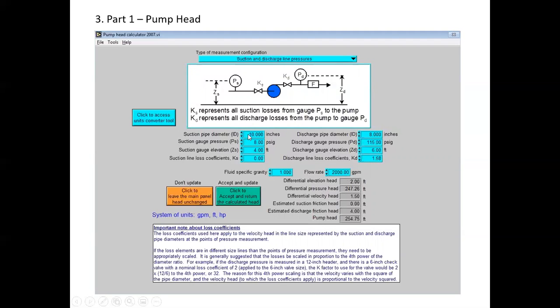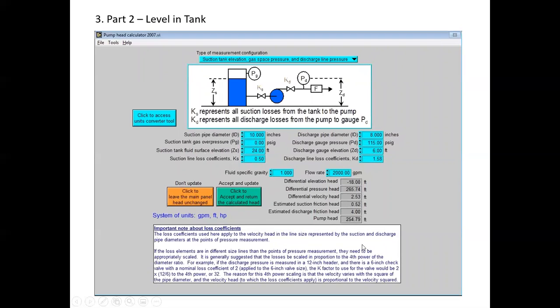At any rate, so I've got 10 inches and 8 inches. I've got 8 PSIG, 115. I've got 4 foot and 6 foot. And on this one, I don't have any fittings between the gauge and the pump. And so I put in 0 here, the 1.58, the 2,000. And I get about 255 feet of head, 254.75 is my feet of head, okay?